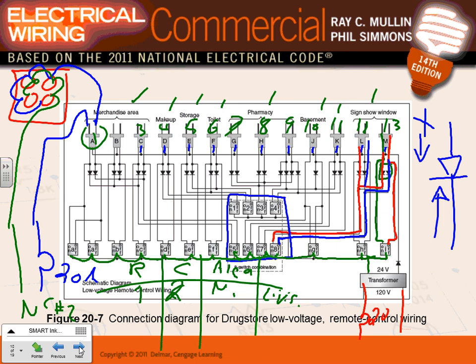I know you guys are not electricians, but the more you know about the whole electrical system, the better you'll be, period. The homework that you guys have has a wiring like this. They ask you to wire it. I strongly encourage you, when you wire it, to keep two things in mind. Number one, you need a common conductor for all the switches, and you need a common conductor for all the relays. That's all. One common for the switches. Can you guys see? And the funny thing is, the common for the relay is where you got your hot here. See how that common is between all the relays, and then for the switches, the other side of a transformer goes to the switches as a common. And then you take two conductors between the relays and the switch. That's all that you're doing. Any comments, any questions, my friends? So that's your lighting control system.